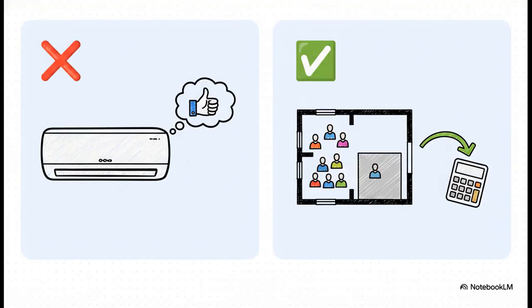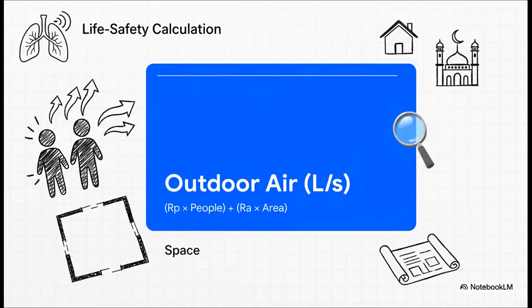Sizing your fresh air with some old rule of thumb, like basing it on the tons of refrigeration, that's an instant fail. It's a direct violation of ASHRAE 62.1 and the Saudi Building Code. There's no arguing this point. The only fix is to do it right. Use the official calculation. Now check this out.